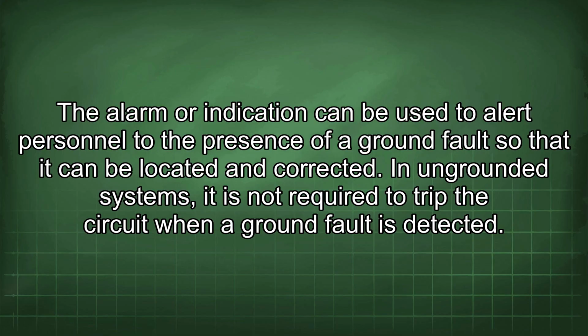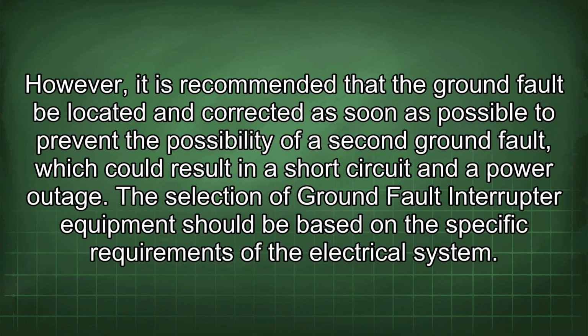In ungrounded systems, it is not required to trip the circuit when a ground fault is detected. However, it is recommended that the ground fault be located and corrected as soon as possible to prevent the possibility of a second ground fault, which could result in a short circuit and a power outage.